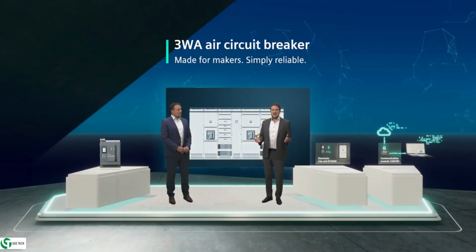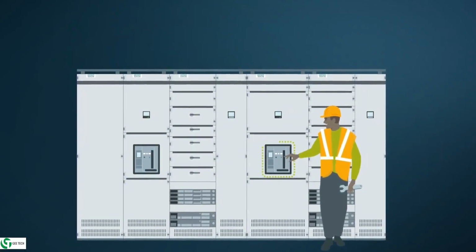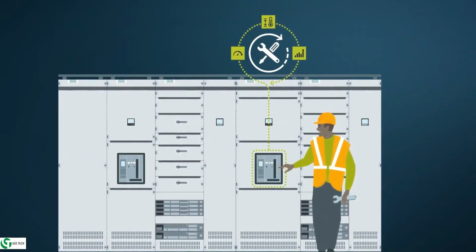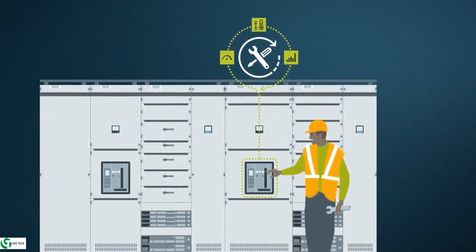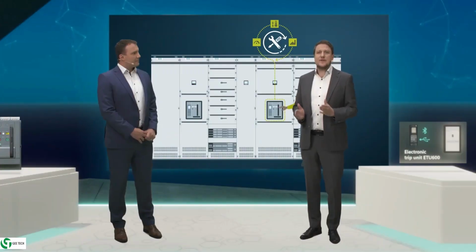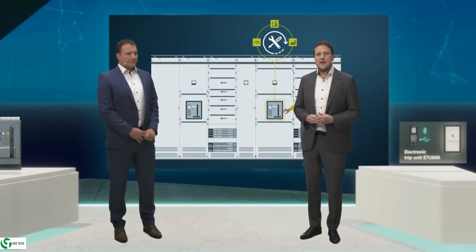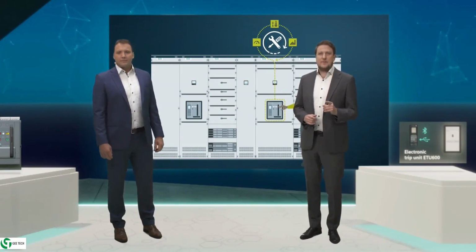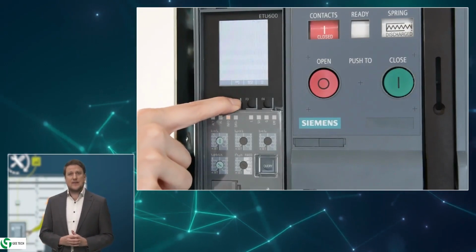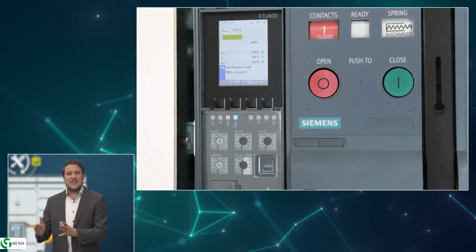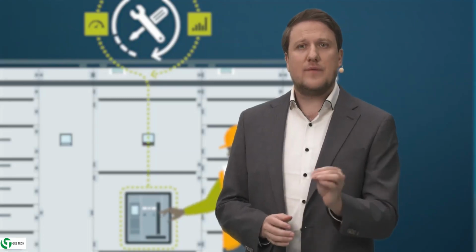The 3WA air circuit breaker is known for its long service life and low maintenance requirements. Thanks to its simple inspection and maintenance, which can be performed on-site by the customer and operators themselves, you significantly reduce your expenses. At the same time, you benefit from longer inspection intervals. In addition, activating DAS+ mode, a new maintenance mode standard in every breaker, while performing your maintenance, will ensure a very high level of personal safety. Why? Because if activated, it automatically reduces all the protection parameters to a maximum sensitive level.